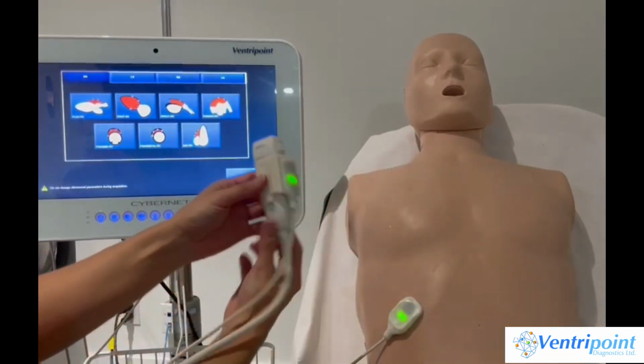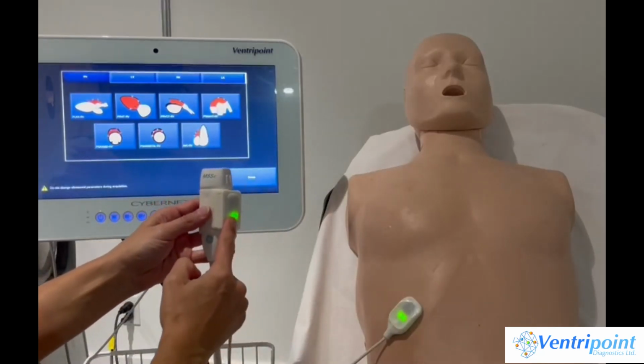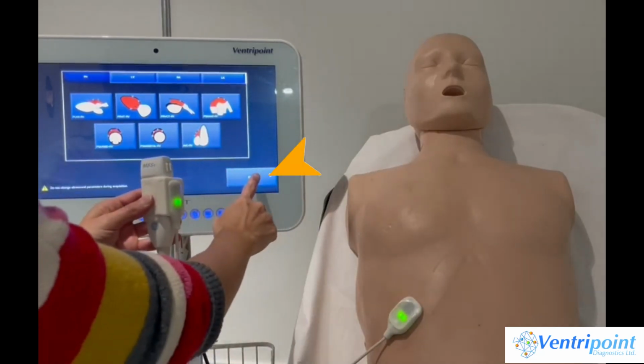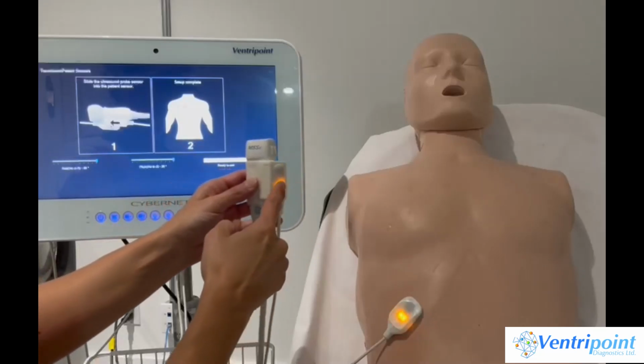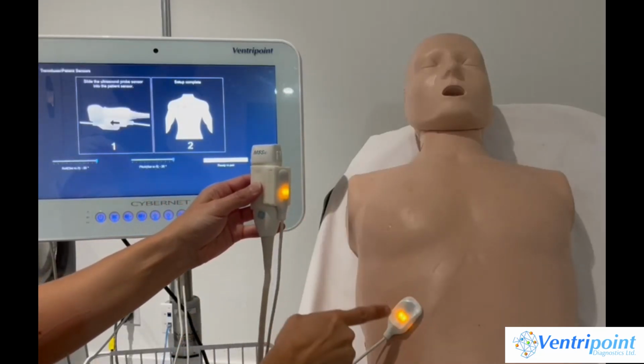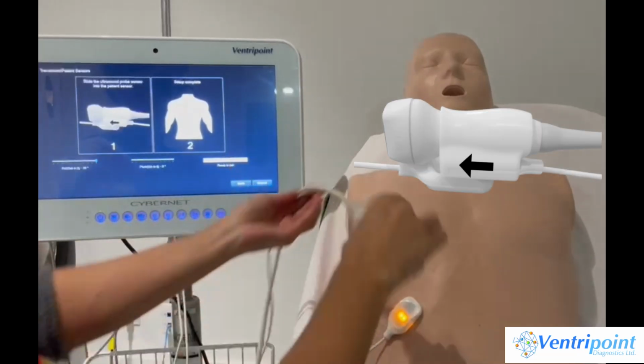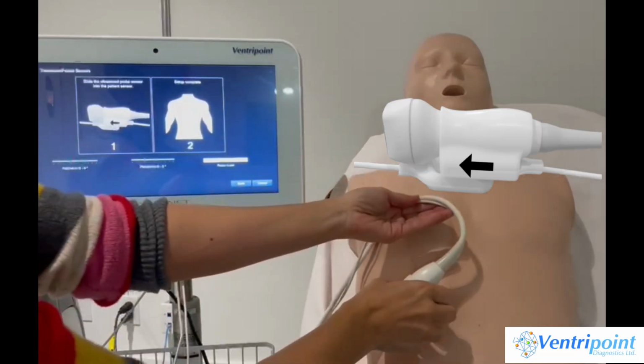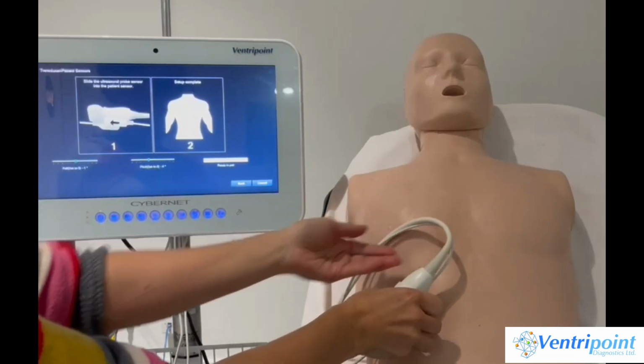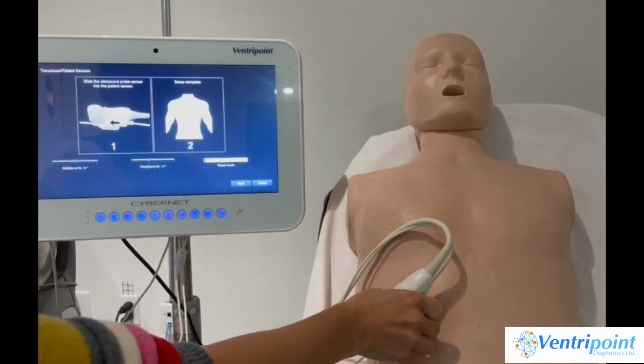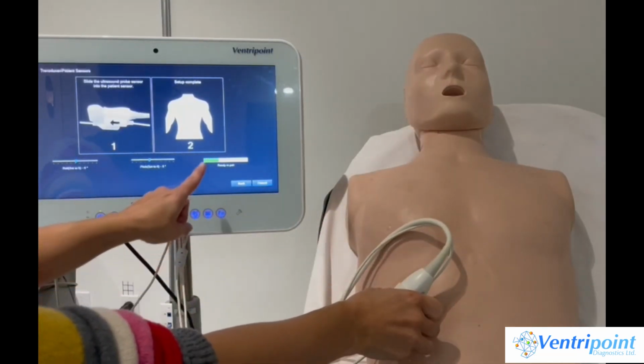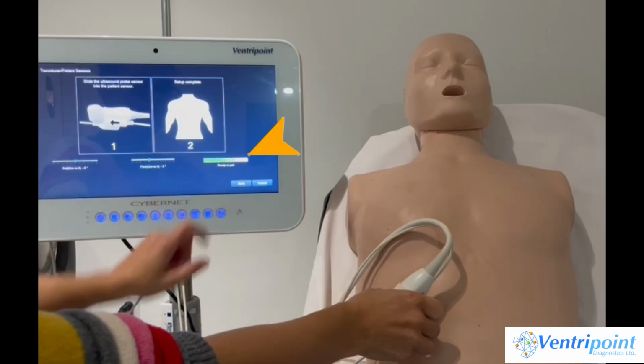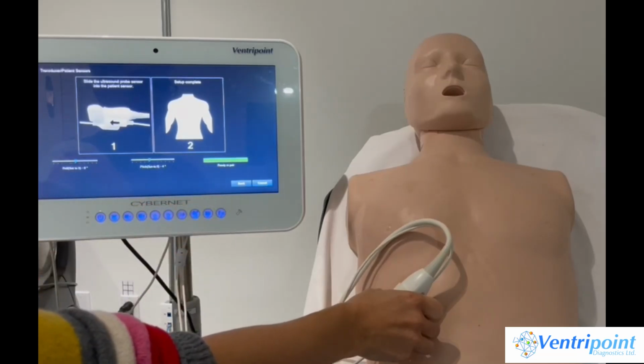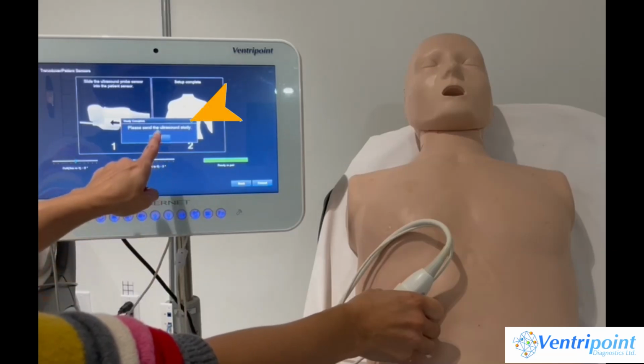Once you have finished your VMS Plus scan, it's time to pair the sensors again. To do this, press Done on the VMS Plus console screen. The sensor lights will then turn amber. Now put the probe sensor and patient sensor into the pairing position. When located correctly, you will hear a soft beep as the pairing process starts. Hold the sensors together as the Ready to Pair progress bar fills. Once paired, you will hear a loud beep, and the save message will appear.